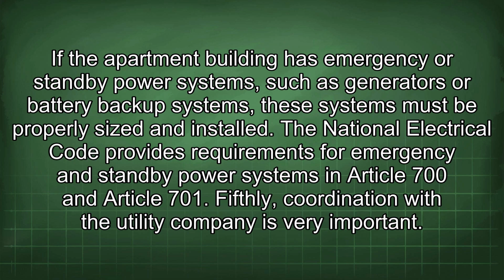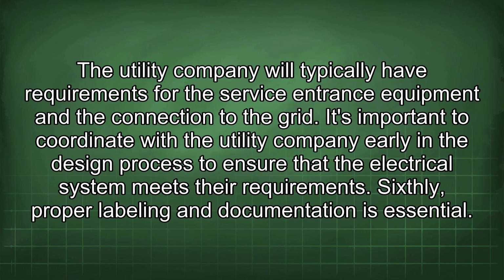Fifthly, coordination with the utility company is very important. The utility company will typically have requirements for the service entrance equipment and the connection to the grid. It's important to coordinate with the utility company early in the design process to ensure that the electrical system meets their requirements. Sixthly, proper labeling and documentation is essential.